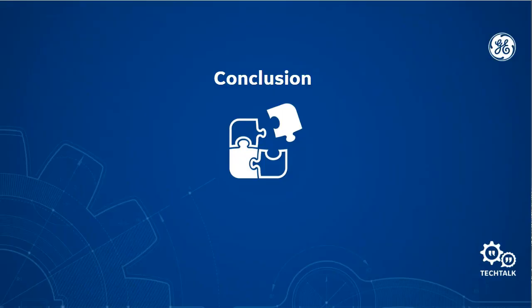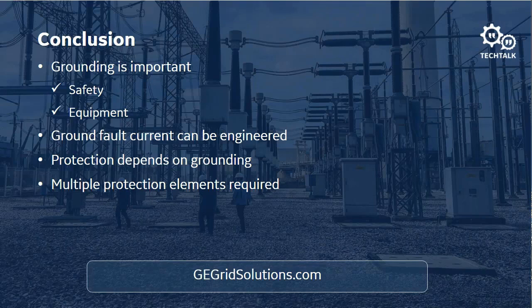So in conclusion, we talked about the various methodologies for grounding. We saw that grounding is very important for safety and for equipment protection. Depending on the grounding method that we use, we can engineer the ground fault current, and the protection will depend on the grounding method. So we talked about the high impedance grounding method, where we use basically the voltage or the injection method to detect ground faults within a high impedance grounded generator. Then for a low impedance grounded system, we talked about the various overcurrent methods that we could use.